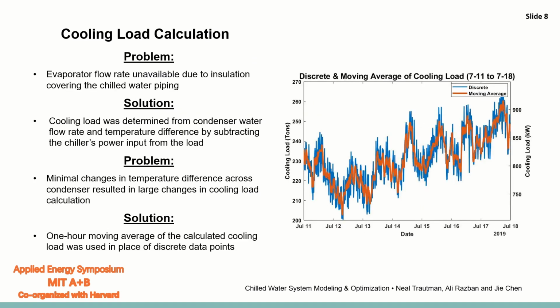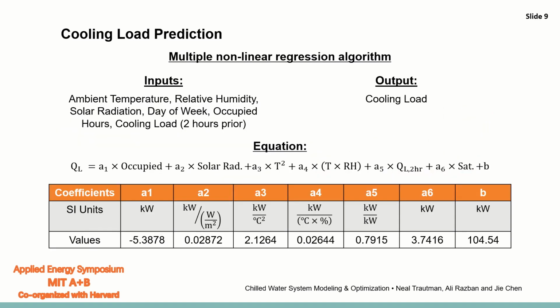Before we get into the cooling load algorithm, I wanted to talk to you about how we calculated the cooling load. The evaporator flow rate couldn't be collected due to the insulation covering the chilled water piping. So instead, we calculated the cooling load from the condenser water flow rate and the temperature difference on the condenser water side of the chilled water system by subtracting the chiller's power input from the load. The difficulty with that is we had a lot of noise in the data that we ended up determining. Small temperature differences across the condenser would result in really large changes in the cooling load calculation. So our solution to that was to use the 1-hour moving average of the discrete data points in order to minimize the noise in the data set. You can see the graph of both the discrete and the moving average of the cooling load on the right, which brings us to the cooling load prediction.